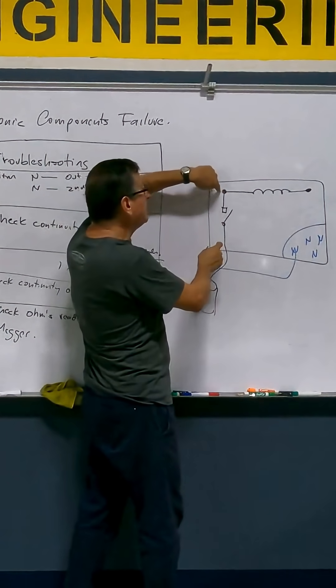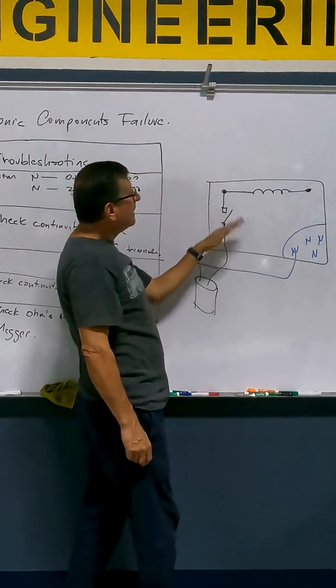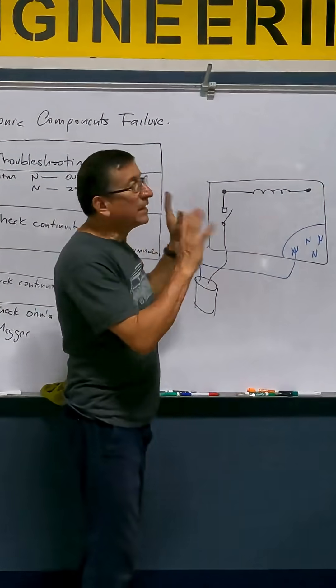What happens if between this and this is open? No continuity. The thermal contactor stays open and the relay is not working.